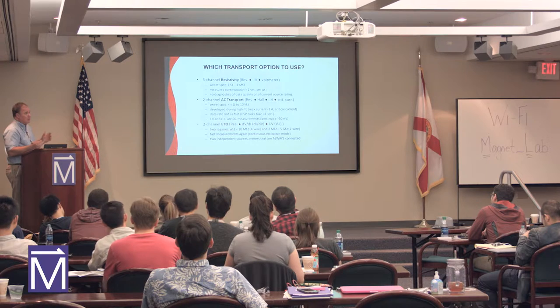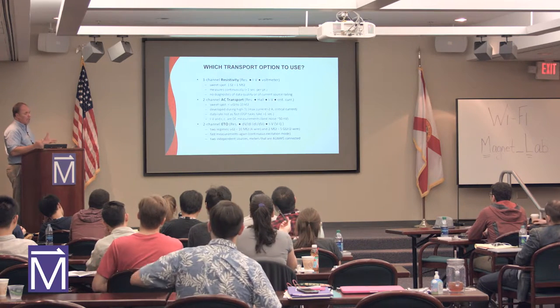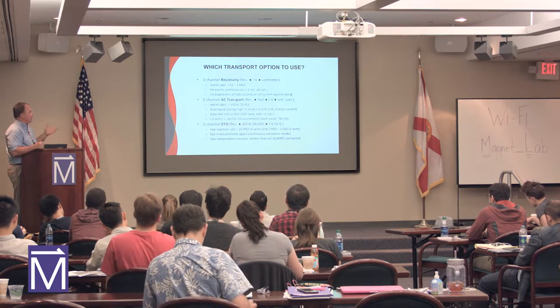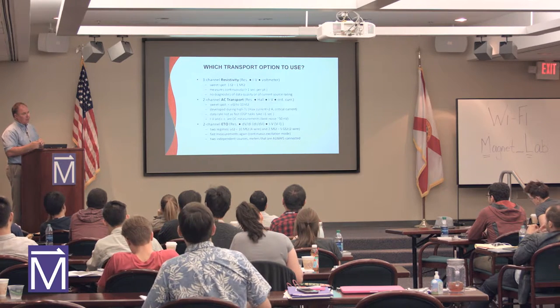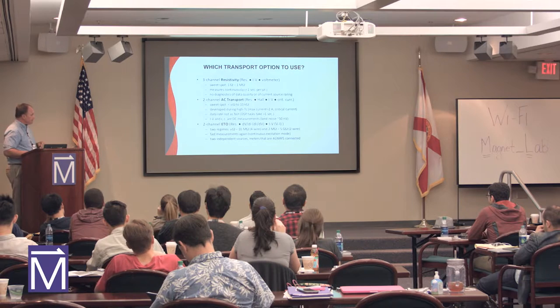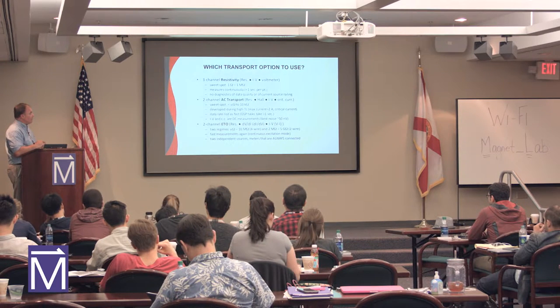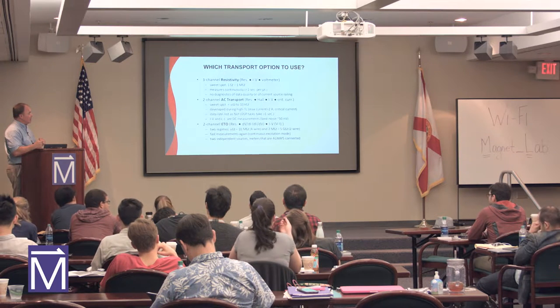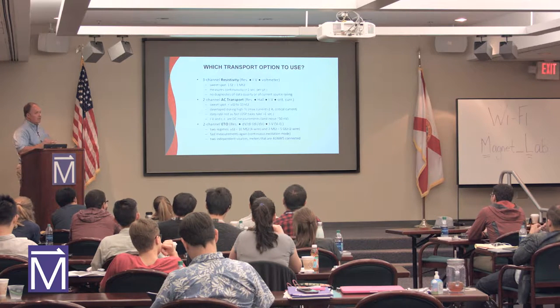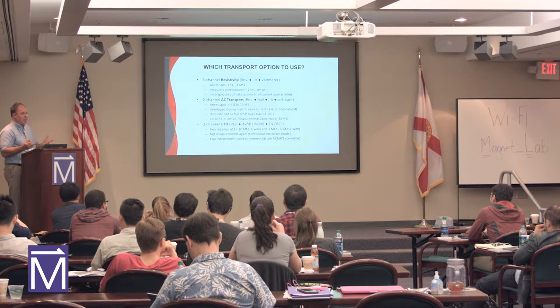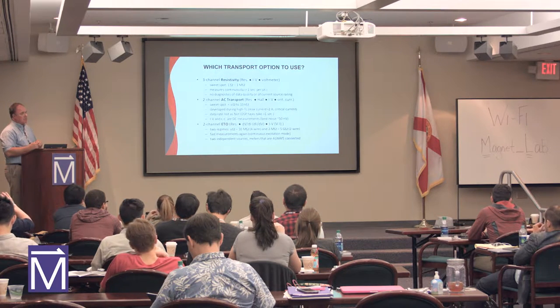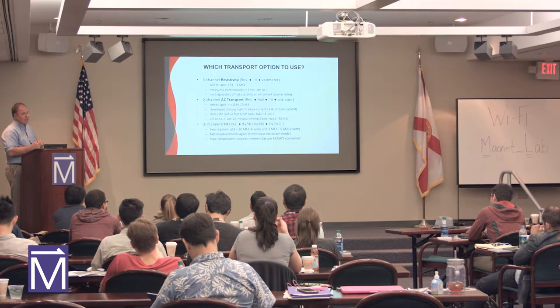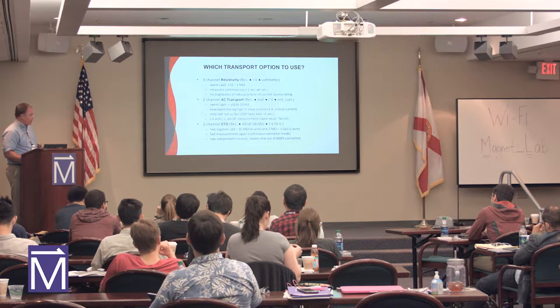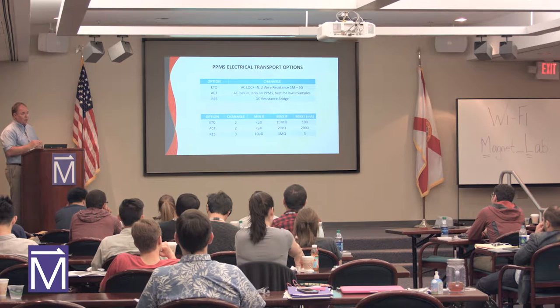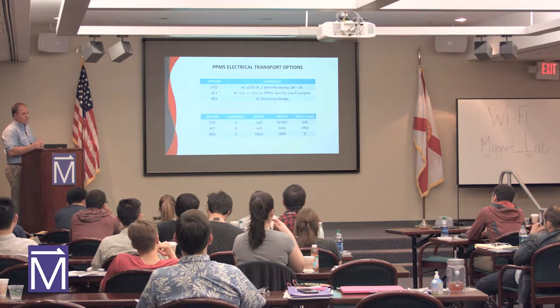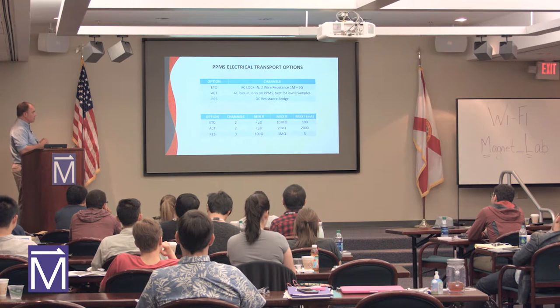So resistivity is a two-wire type measurement, IV curve, essentially a voltmeter. AC transport does critical current measurements, resistivity and Hall effect. ETO does resistivity and Hall effect, and we've got a couple of other types of measurements that you can add on to the ETO that we'll talk about. Resistivity is measuring at less than 0.1 per second. The AC transport has a DSP technique in it, similar to the lock-in techniques you heard about, with a modulated signal. So it takes a little over a second to take each data point. The ETO is a faster measurement, with faster processing technology and a couple of different independent sources and voltmeters, similar to what you would do for a nanovoltmeter type experiment.